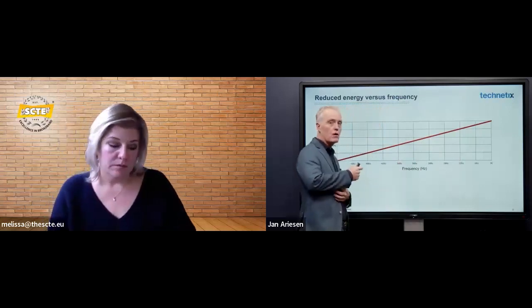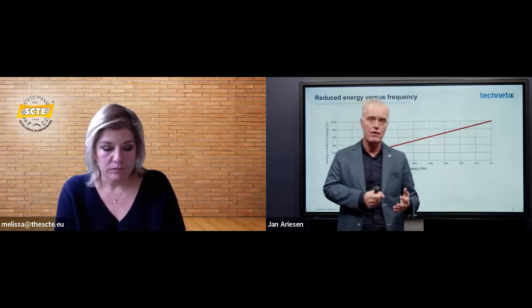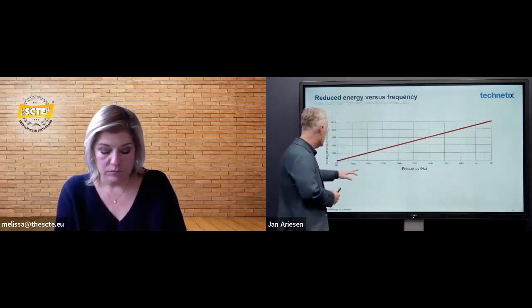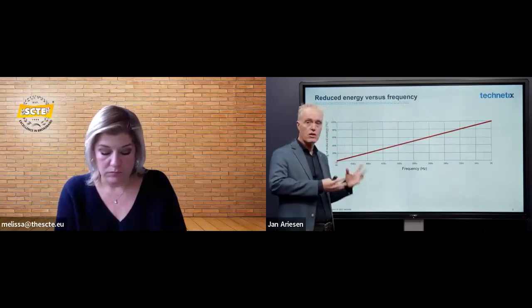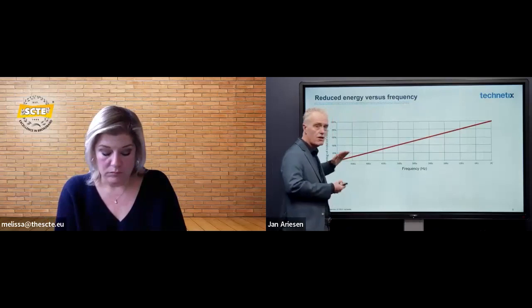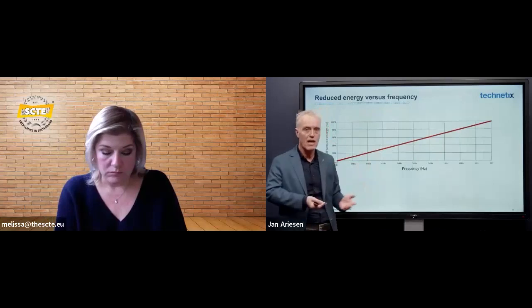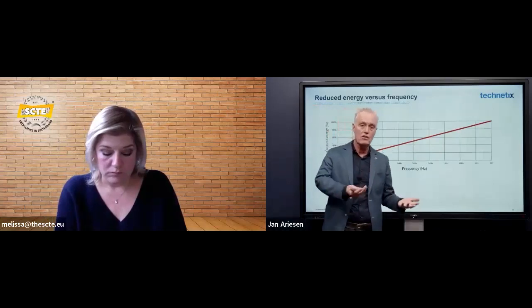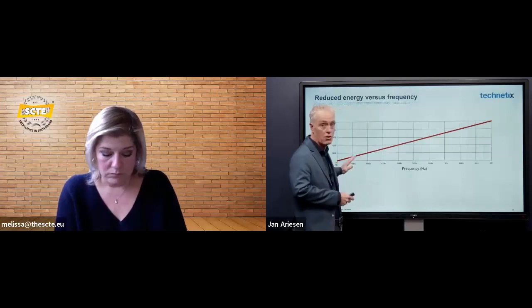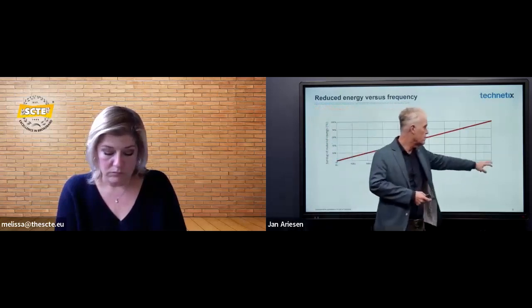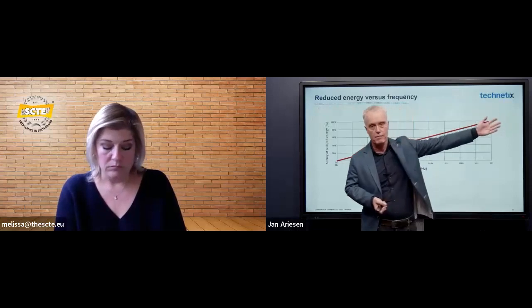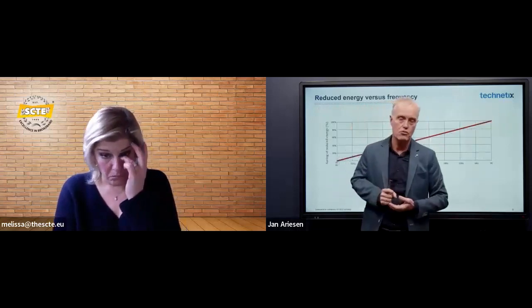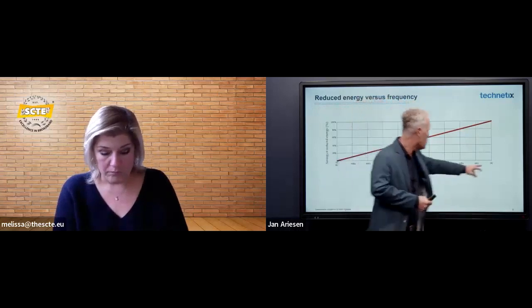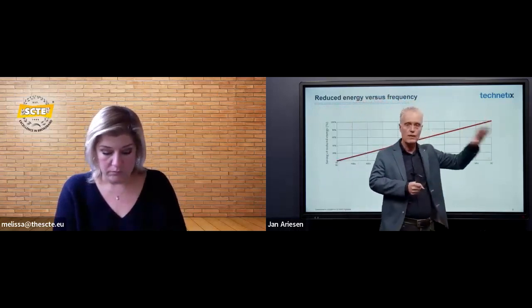First we looked into the saving. What is the saving that we get? Let's say we have 60 Hz for the US or 50 Hz in Europe, and the saving at that moment is 0 - it's the same, this is just comparing DC versus AC. So if I switch at 50 Hz, I have the same as a 50 Hz sine wave, so no saving at all. If I go to full DC, I have 100% of my saving. In my previous example, I showed a saving of 26%, so with DC we have a full 26% saving.